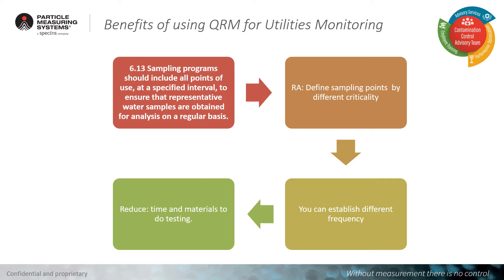What are the benefits of using quality risk management for utilities monitoring? Our sampling programs should include all points of use at a specified interval to ensure that representative water samples are obtained for analysis on a regular basis. Our risk assessment helps us define sampling points by different criticality. For example, WFI as a raw material is much more critical than WFI as a final rinse in our CIP cycle, so we can establish different frequencies based on that risk. This helps us reduce time and materials for testing, but more importantly helps us ensure that we're sampling at areas of greatest risk to our products.